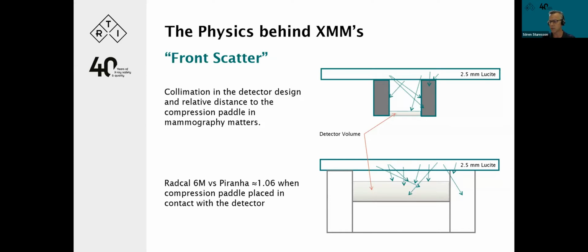That is also the case for ion chambers, depending on the ion chamber design, depending on how deep the sensitive volume is placed in an ion chamber. A plane parallel chamber with a detector volume directly up to the surface will be the most sensitive to front scatter, whilst others that have different kinds of position placement of the sensitive volume will also lose some information in terms of front scatter. Also important to be aware of.